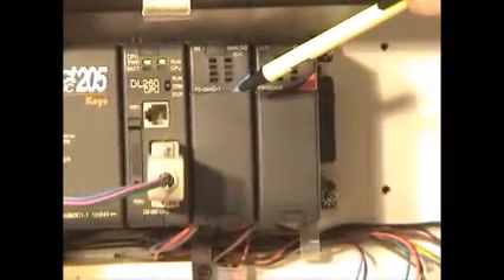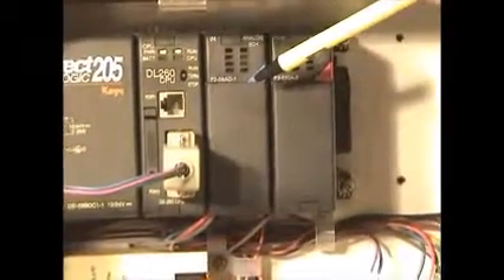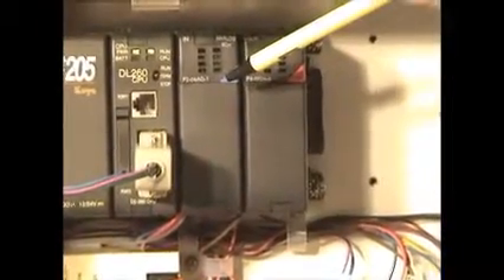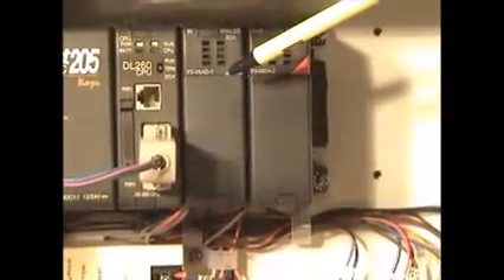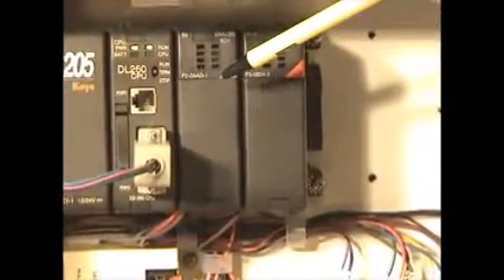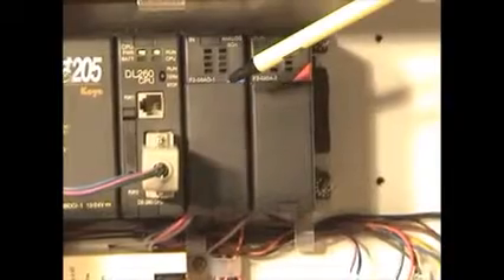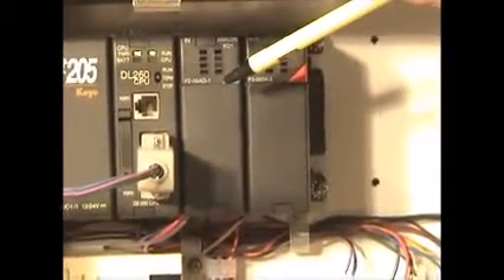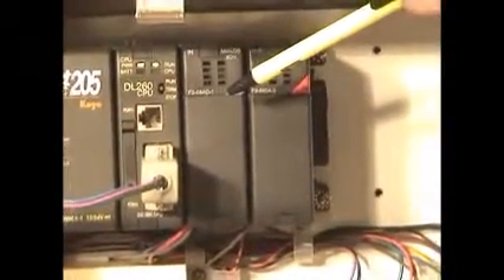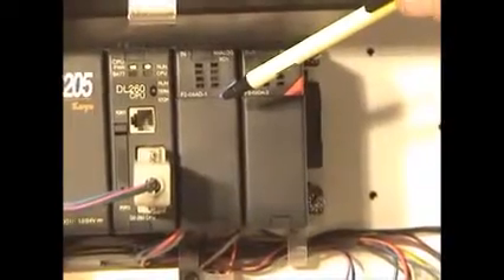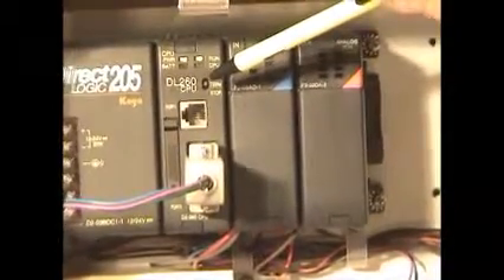This module gathers a 4 to 20 milliamp value from the pressure transducer, the vacuum transducer, the velocity meter, the temperature transducer, the hydraulic open and close pressure transducers, and, if installed, the optional depth transducer. It sends this information into the CPU module so that these values can be displayed on the Dredgemaster monitor.